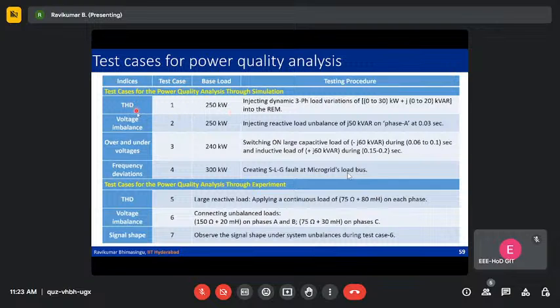That is one test, and voltage imbalance, how it is affected. When injecting a reactive load unbalance, we considered phase A. At around 0.03 seconds we created an unbalance, a reactive power load unbalance of 50 kVAr. To check the over voltage and under voltage indices, a large capacitive load is switched on and off, and an inductive load is turned on and off, and frequency deviations are measured.